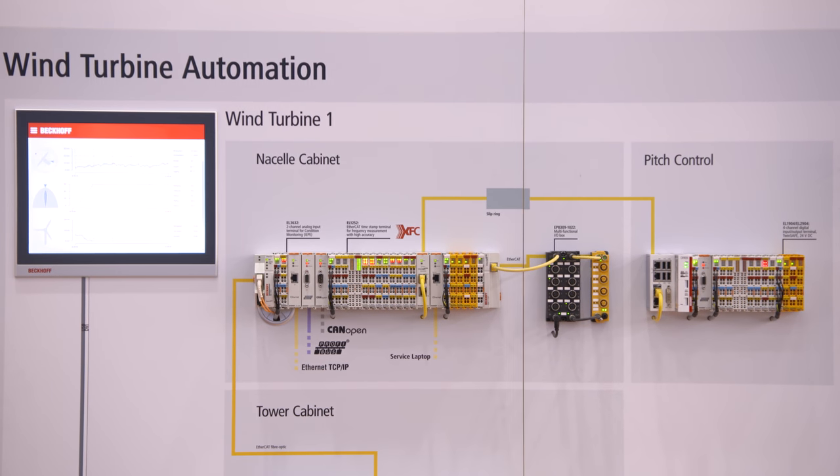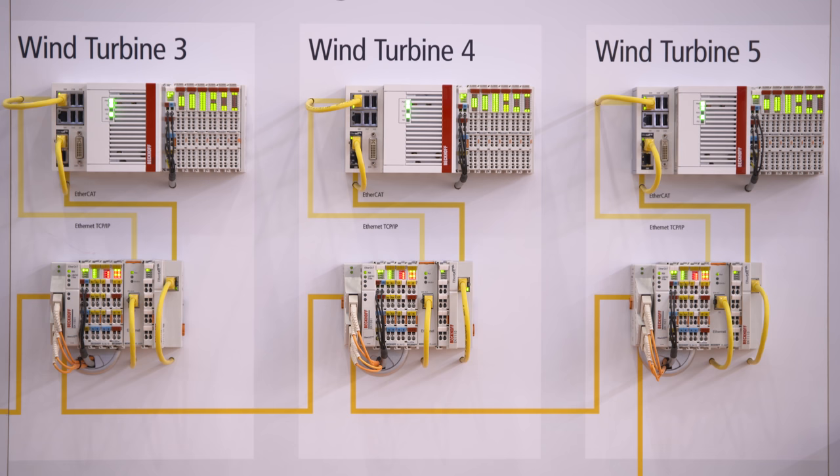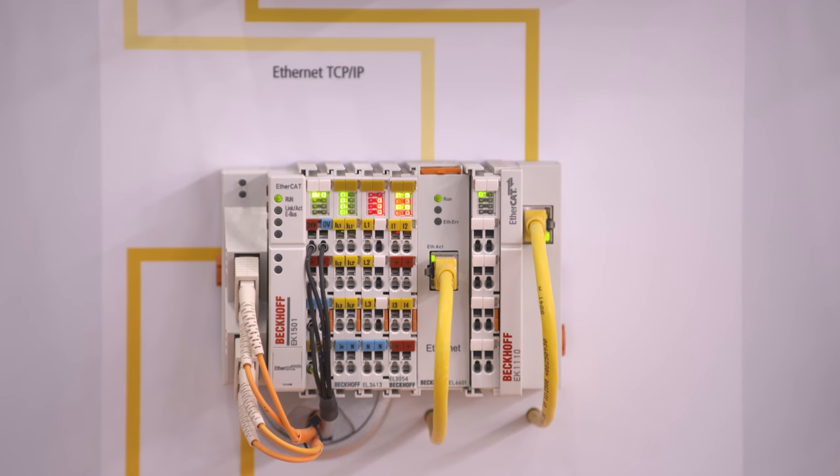EtherCAT can communicate with fieldbus-based protocols to other subsystems, and also across the whole wind farm to create a collective reaction at the point of common coupling if there is any issue — such as a low voltage ride-through or high voltage ride-through — and share all new set values across all turbines within less than a millisecond.